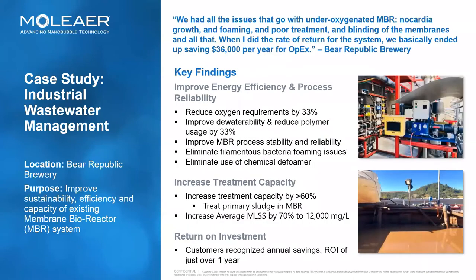Following the installation of the two Moleaer XTB 200 nanobubble generators, the system showed quite a few improvements. They reduced oxygen requirements by 33%. They improved dewaterability and reduced polymer usage by 33%. The MBR process stability and reliability greatly improved. The foaming issues were completely eliminated, which allowed them to completely eliminate the use of chemical defoamers. They increased the treatment capacity by greater than 60%. They brought up their mixed liquor concentrations to 12,000 milligrams per liter, a 70% increase over how they were previously operating. The customer reported a $36,000 per year OPEX savings, representing an ROI of just over a year following the installation of our equipment.